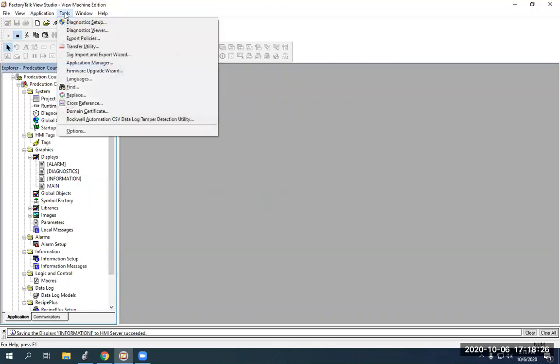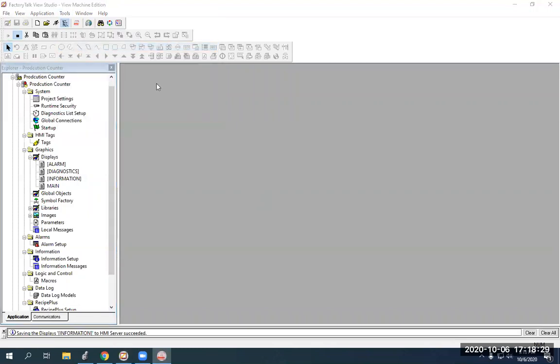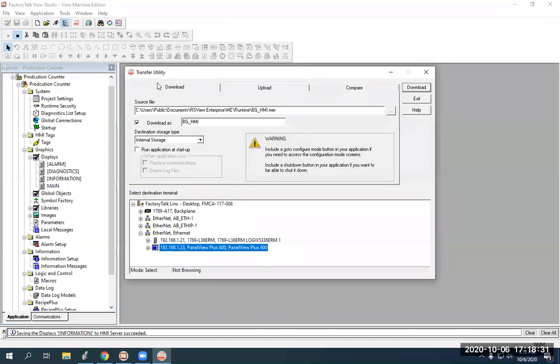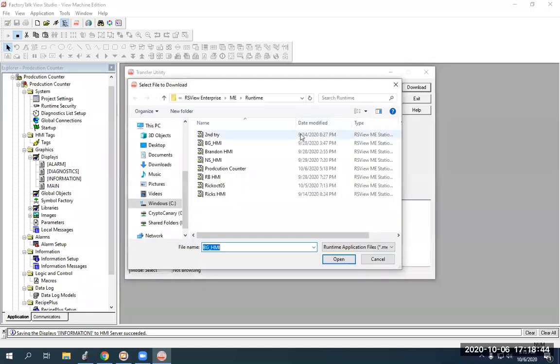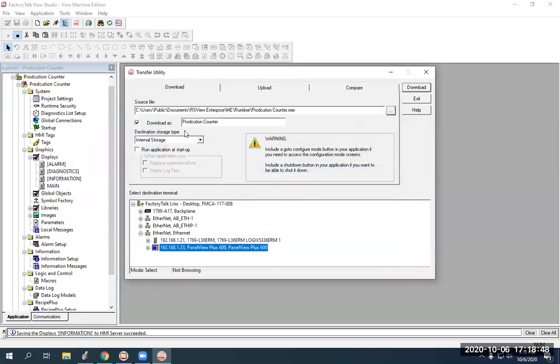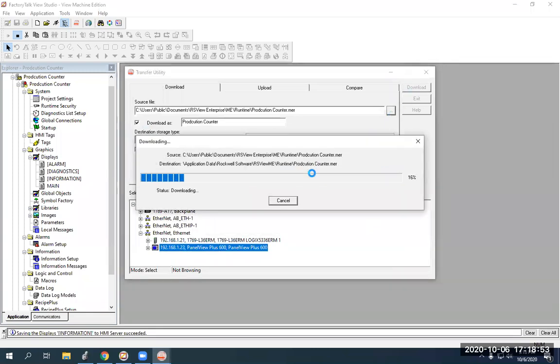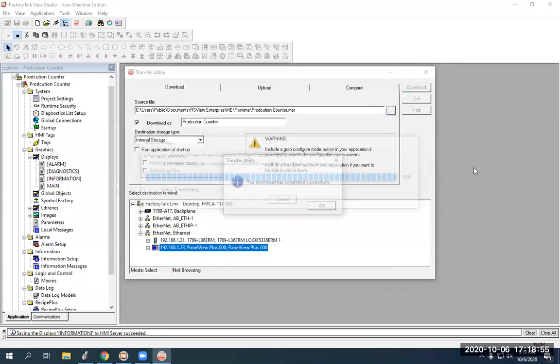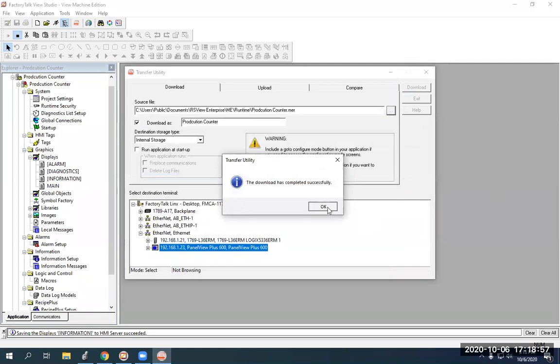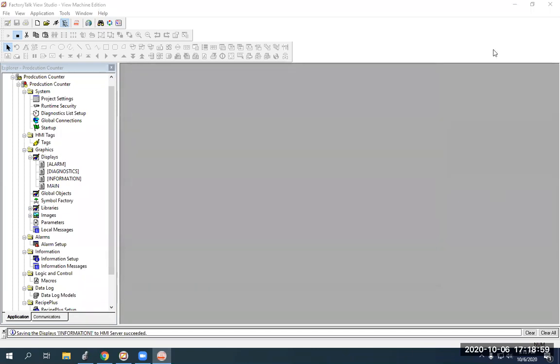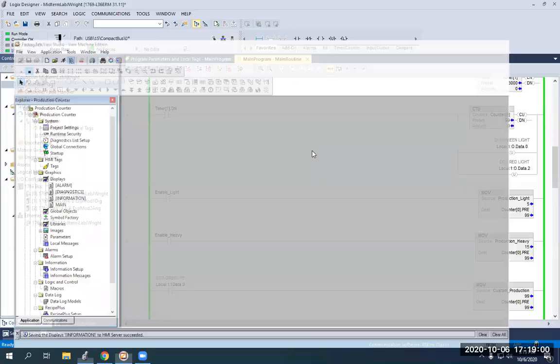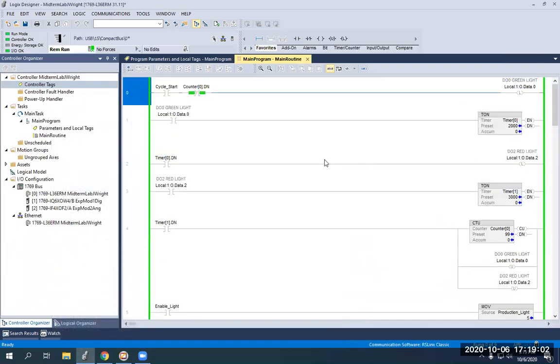All right. So, now we're going to go to tools. We're going to go to transfer utility. Then we need to highlight our panel view plus 600. That's what we're moving them to. We are moving it to internal storage. But here, we are not downloading BGHMI. We are downloading production counter. And it's downloading as saving to internal storage on panel view. Just hit download. Now it's moving it over to my panel view. All right. So, I can just close here. I'll just minimize this. And now we're in our PLC program.